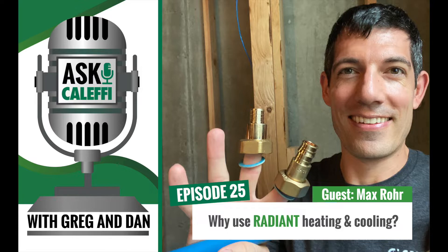We do get a lot of questions about application. We don't really design systems, but myself and Max have a background of installing and working with PEX and radiant systems. The first thing we want to talk about is why use radiant heat. I love radiant because it's one of those few things in life that, when done well, is a great mix of comfort and energy efficiency. You get both at the same time. You can hide it in the floors, the ceilings, the walls, and you can use all sorts of different heat sources. It's kind of future-proof in the sense that you could use a non-condensing boiler with a boiler protect valve, a condensing boiler, or an air-to-water heat pump over the course of the life of the system. Big picture, it's about 30% energy savings compared to forced air when installed well.